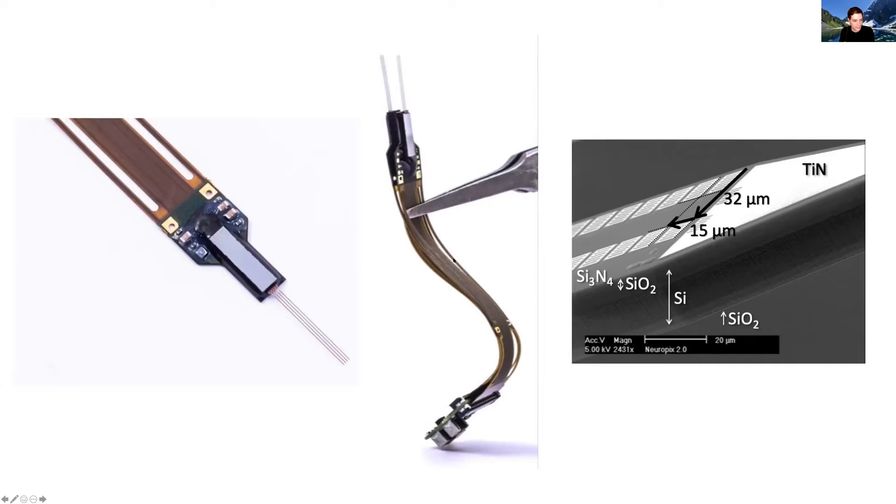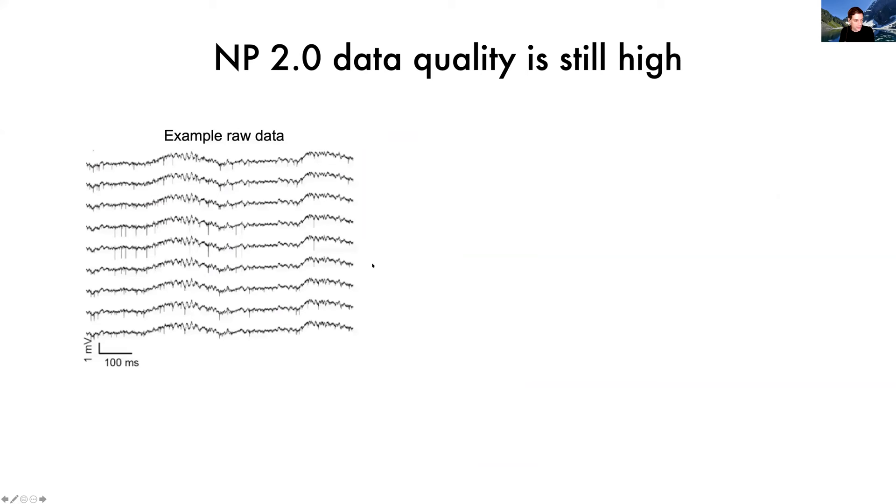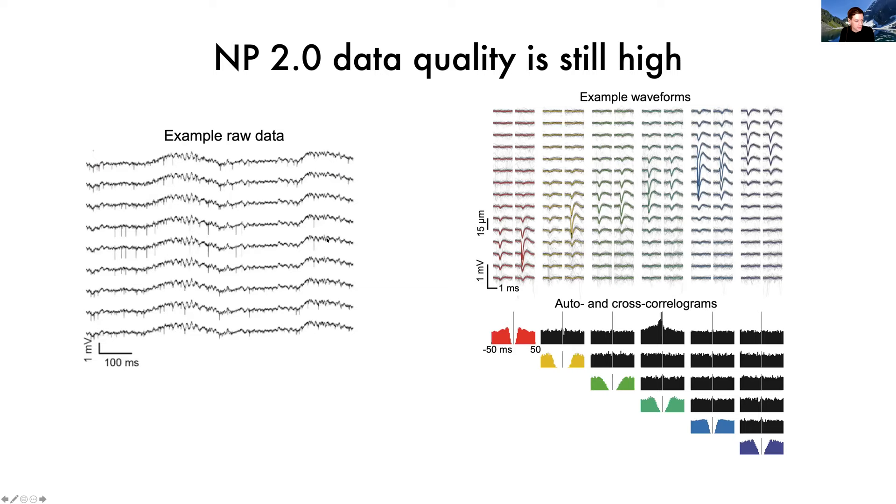One of the main points of 2.0 probes is that because they're so small and light and two of them can fit on a head stage, you have the ability to, with less than one gram of implanted hardware, this two probes plus head stage weighs about one gram. You can implant two of these probes and record 768 channels simultaneously in a freely moving mouse or in a chronically implanted mouse. The data quality is still very high. Here's just a figure from our paper where we show some raw data with local field potentials and spiking data and some isolated single neurons with high quality waveforms and isolations. So even though the probe was miniaturized, there was no appreciable change in the data quality.